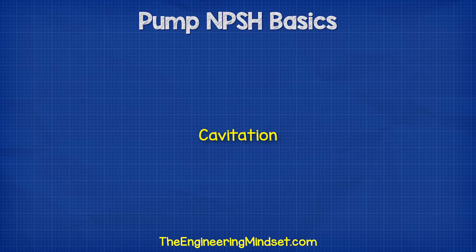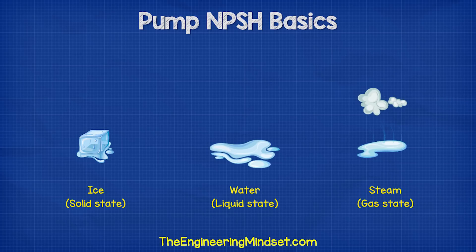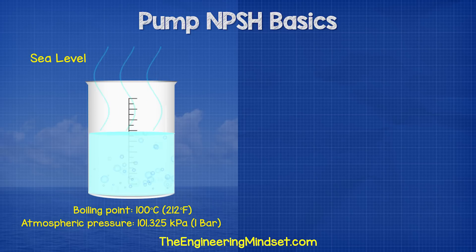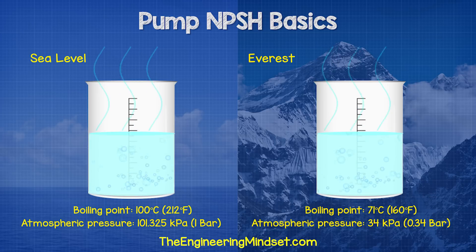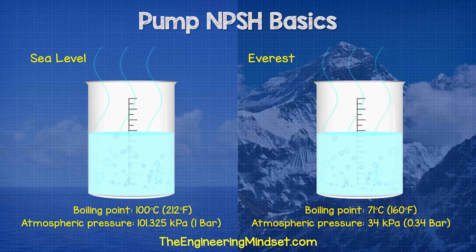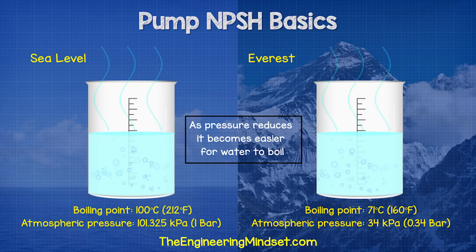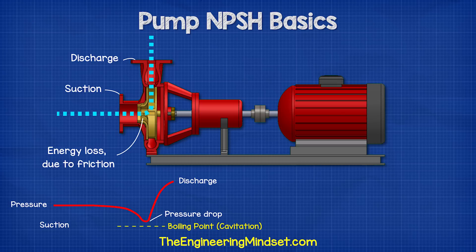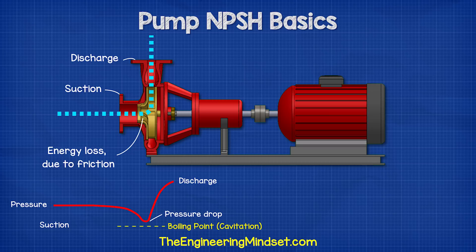So what is cavitation? Water can turn from a liquid state into steam or a gas state. We know that water boils at around 100 degrees Celsius at sea level, which has an atmospheric pressure of 101.325 kPa. But if we went to the top of Mount Everest, water boils there at just 71 degrees Celsius because the atmospheric pressure has reduced to 34 kPa. As atmospheric pressure reduces, it becomes easier for water to boil. At the suction inlet of the pump, there is going to be a pressure drop, and if this pressure is less than the vapor pressure of the liquid being pumped, the water can reach boiling point — when this happens, cavitation occurs.